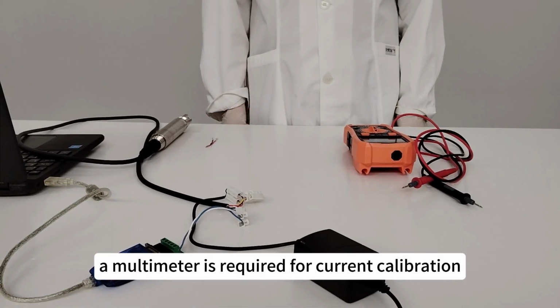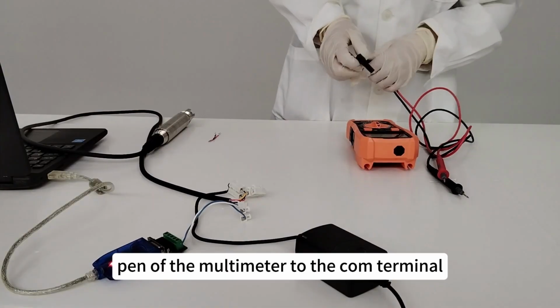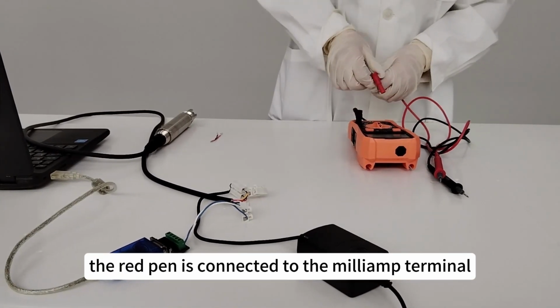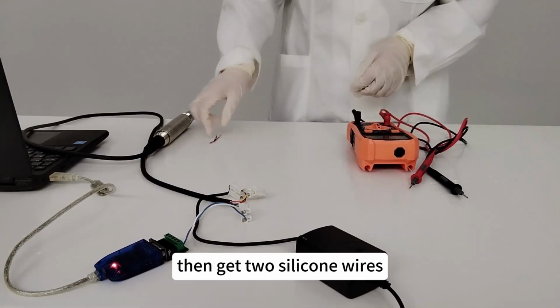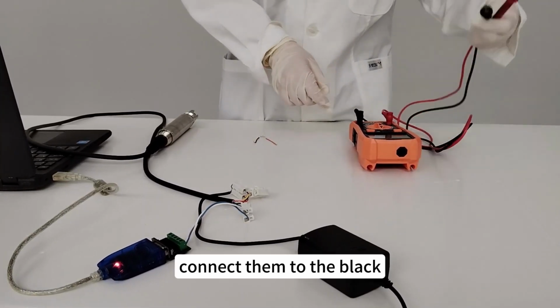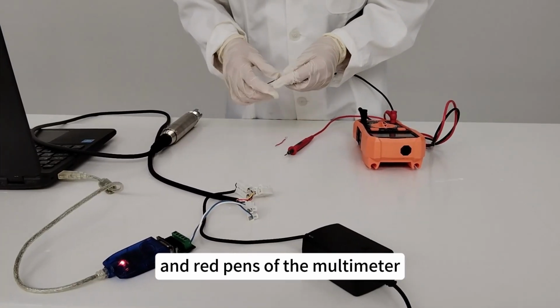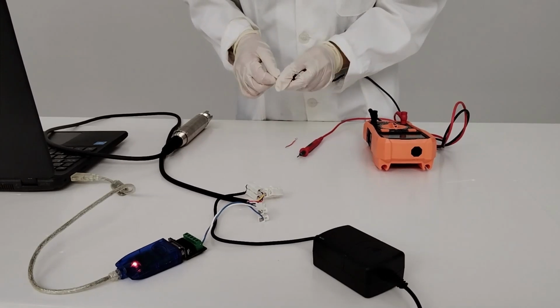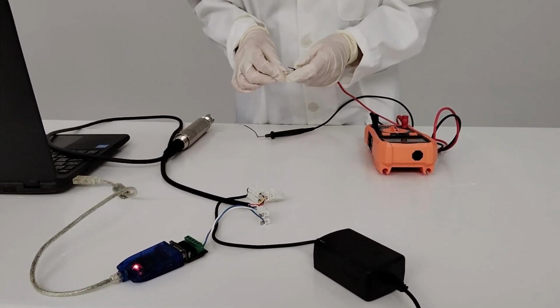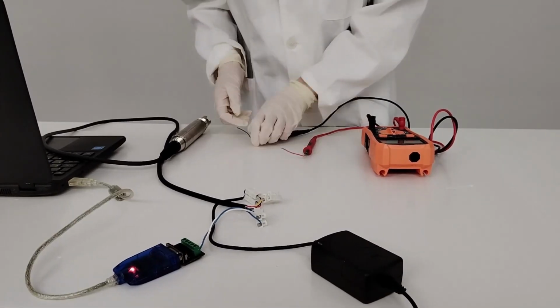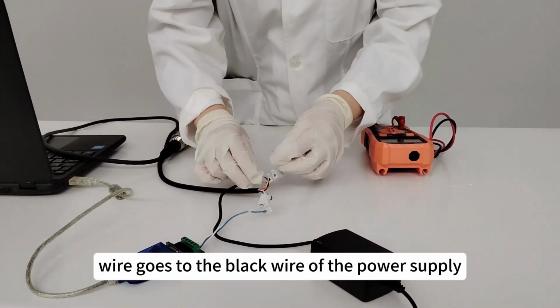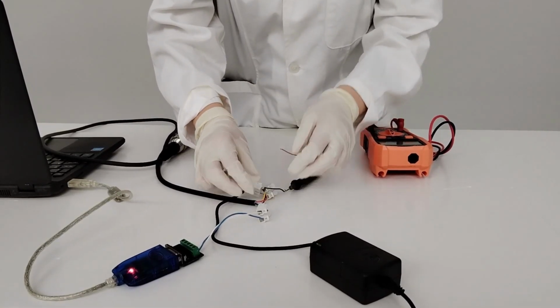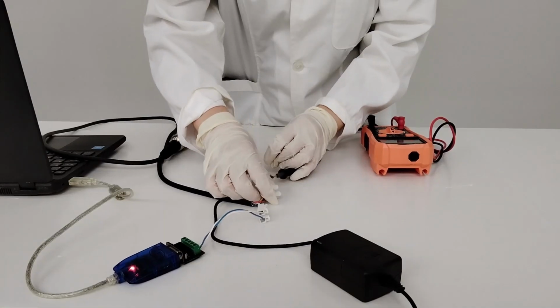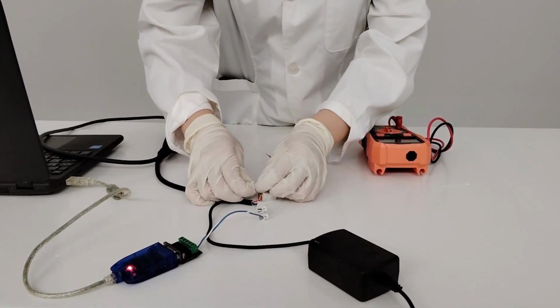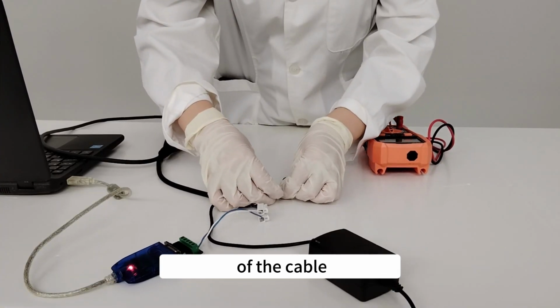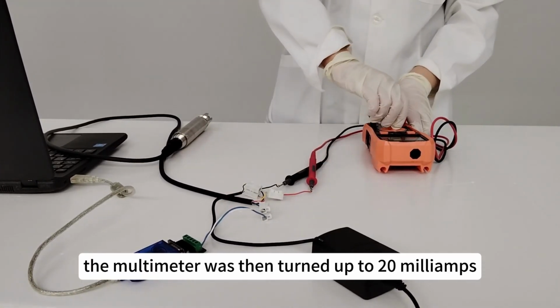A multimeter is required for current calibration. Connect the black pen of the multimeter to the COM terminal. The red pen is connected to the milliamp terminal. Then get 2 silicone wires and connect them to the black and red pens of the multimeter. The other end of the black wire goes to the black wire of the power supply. The red wire is connected to the yellow wire of the cable. The multimeter is then turned to 20 milliamps.